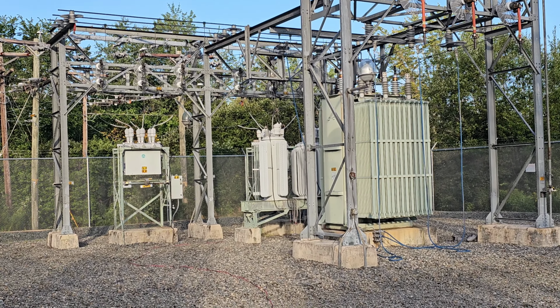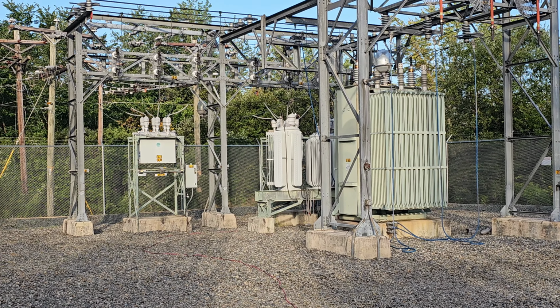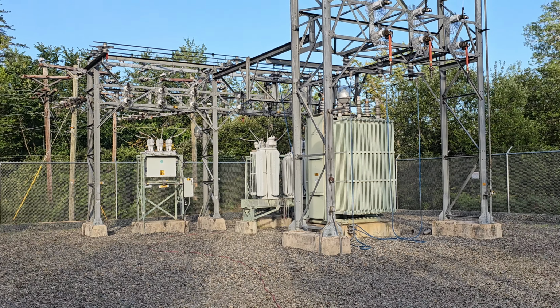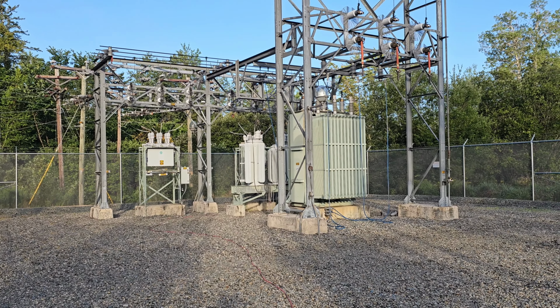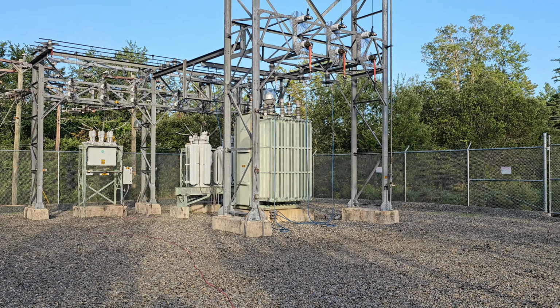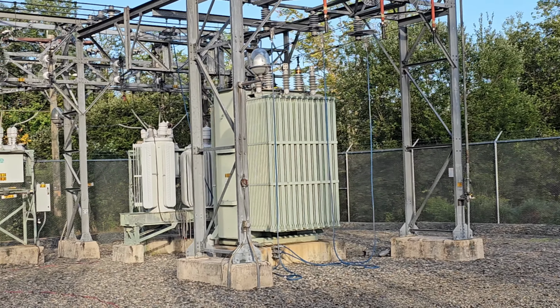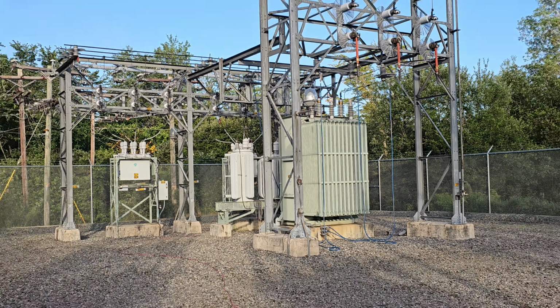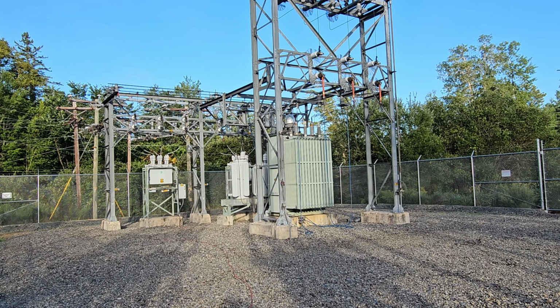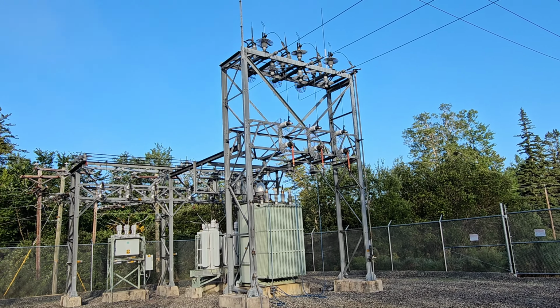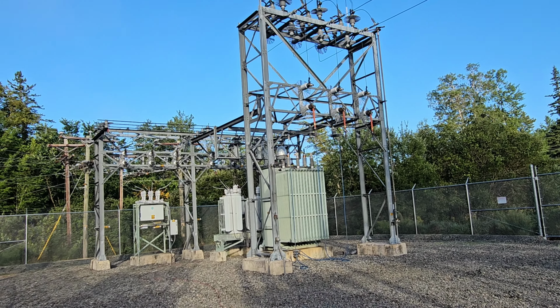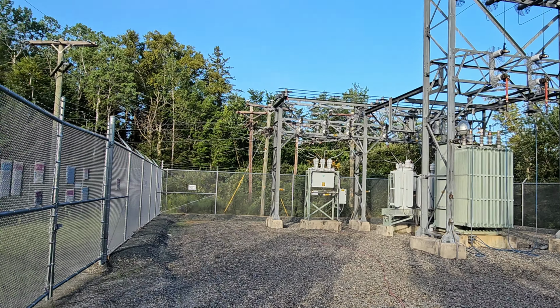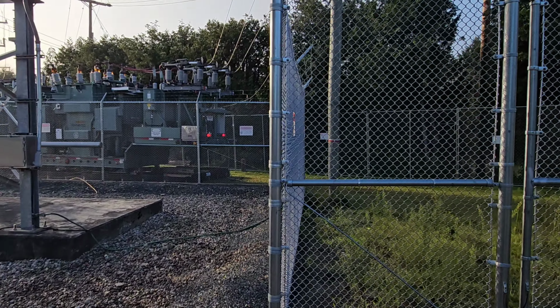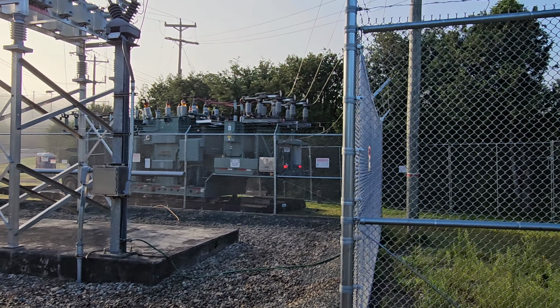So in the event of a fault, everybody on those two combined circuits will be out of power. But it works for the purpose of doing the maintenance here in the substation for a temporary amount of time. Everyone can maintain their service, and this can be put back into service should an emergency arise. And so that's why there are mobile substations, and that's what they do.